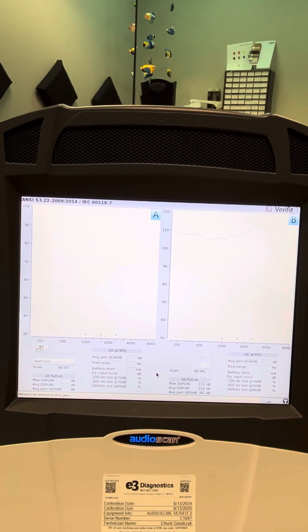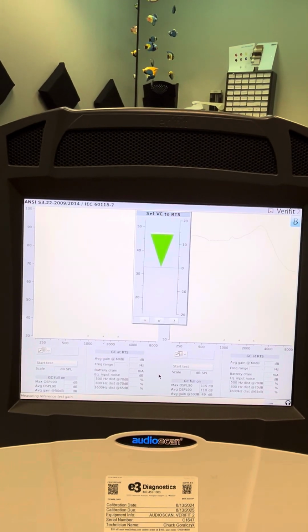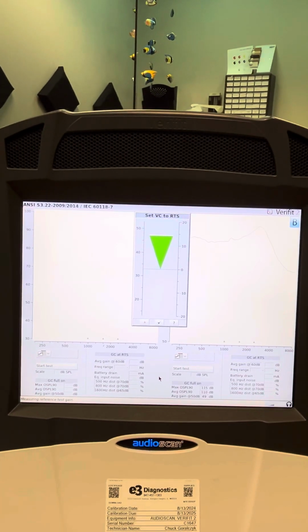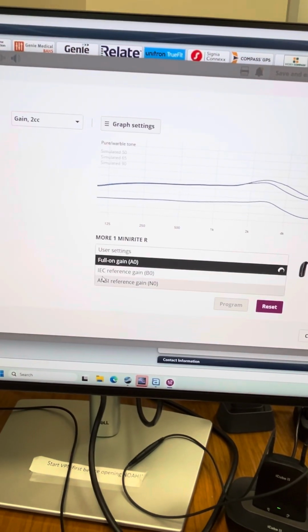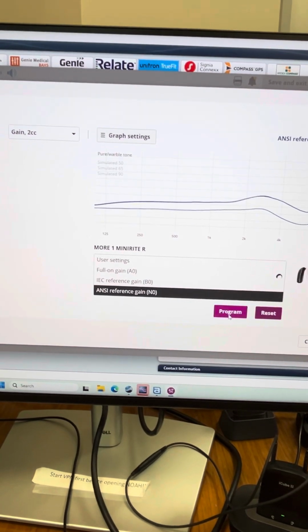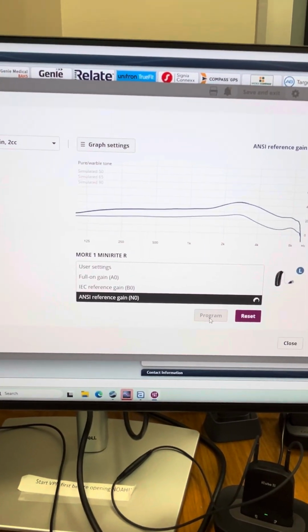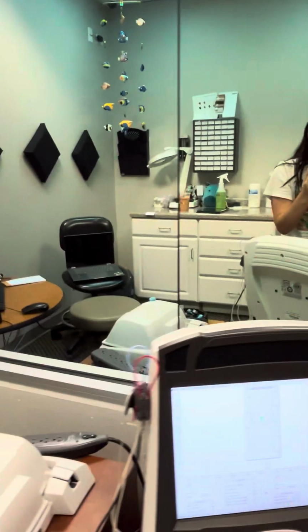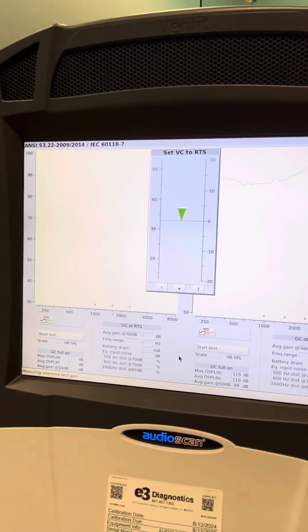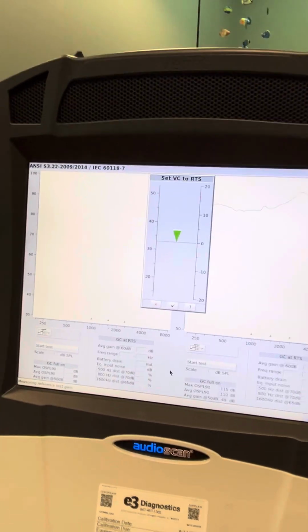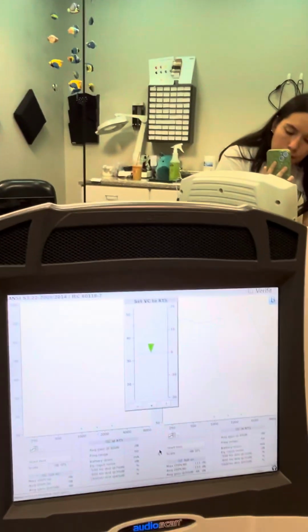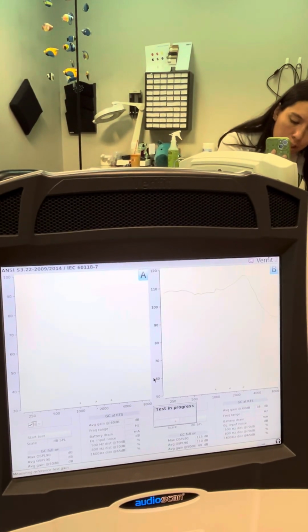And now we have the big pizza, so we have to make it a smaller pizza. So that's when we come back over to our computer and we're gonna switch it to ANSI reference gain and program it. And now when we come back over to the Verifit, the pizza should be smaller. So we have our ANSI reference test gain. Perfect. So now we have our smaller pizza and we're gonna hit check.